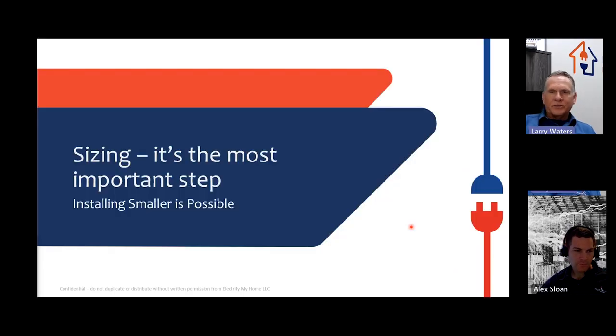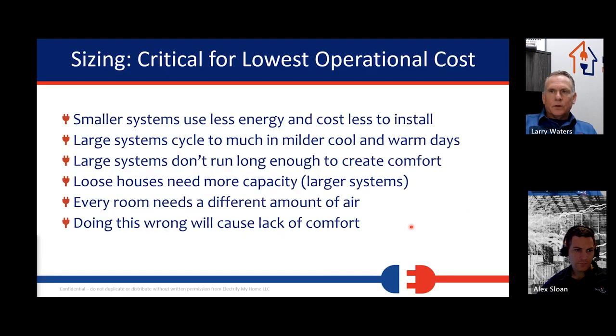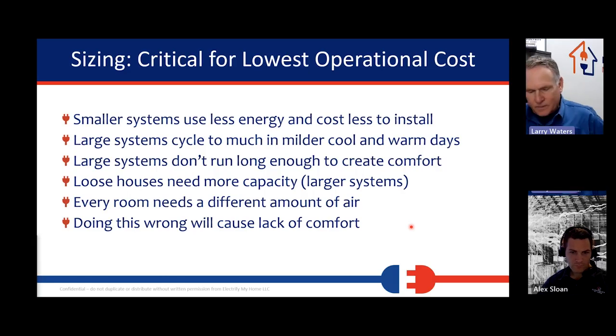Okay. Sizing, the most important step. Smaller systems use less energy and cost less to install. So if I'm up against doing a change out, like a service tech goes out and says, we're going to put in a new furnace and air conditioner, 3-ton with a new coil. I don't even know. I don't do any of that work anymore, but that's a specific amount of money for that equipment. If you look over at what's available with inverter equipment, like the mini split based ducted equipment, they're very inexpensive in relation to that. And we can really ramp those up and make them perform better much more easily than you can a traditional unitary system. So you have a lower cost of installation.